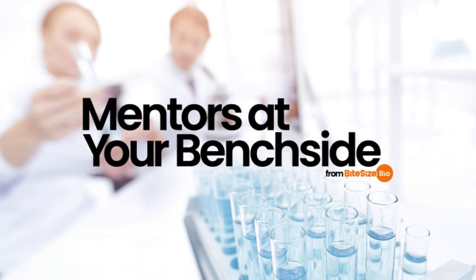So each time you weigh a sample, your scale should give you the same weight within a certain margin of error. And this accuracy is stated in your scales manual, or it can be found on the manufacturer's website. Now you place and remove the sample 10 times and record each reading as soon as the balance indicates that the reading is stable.